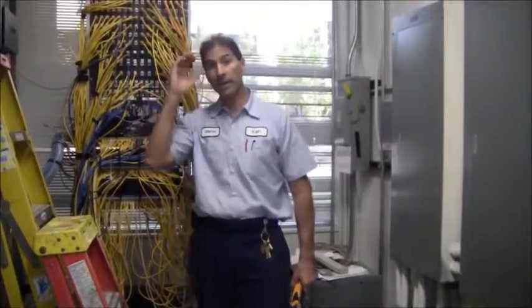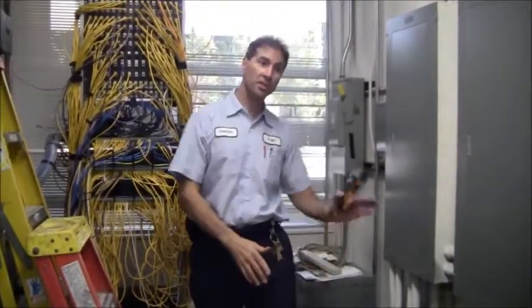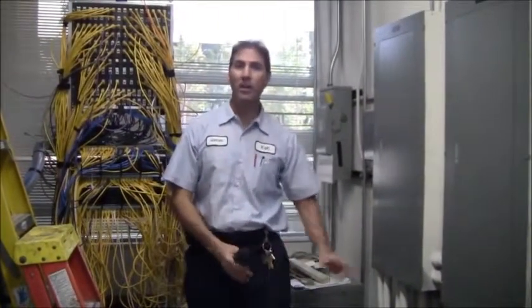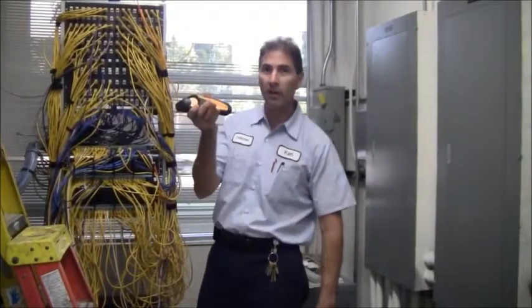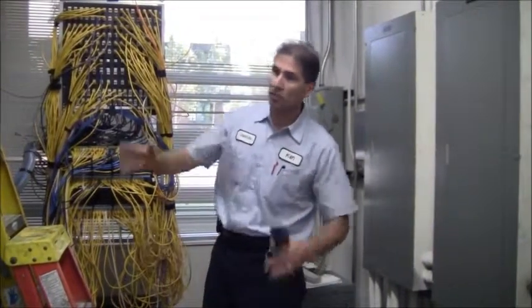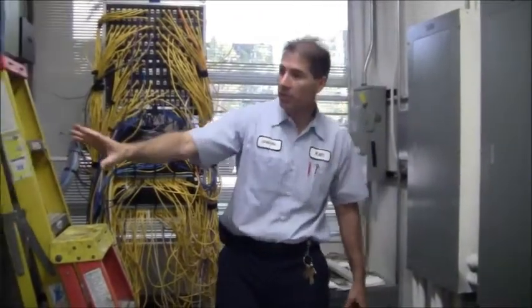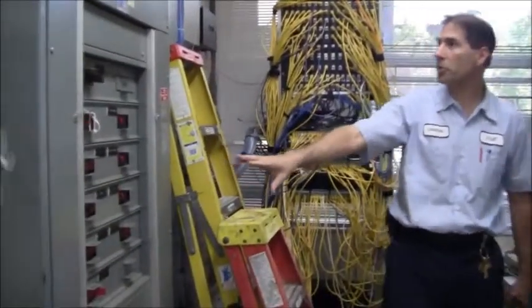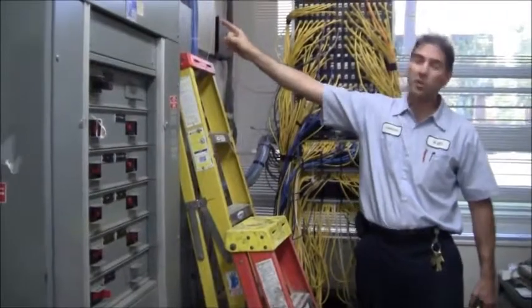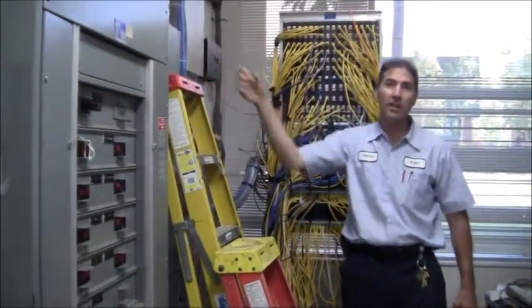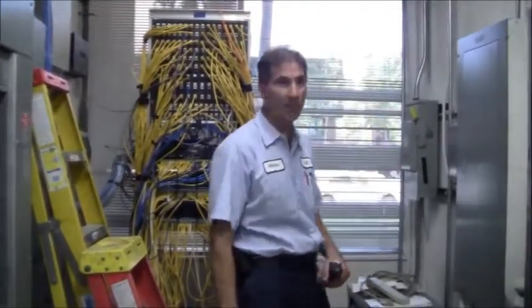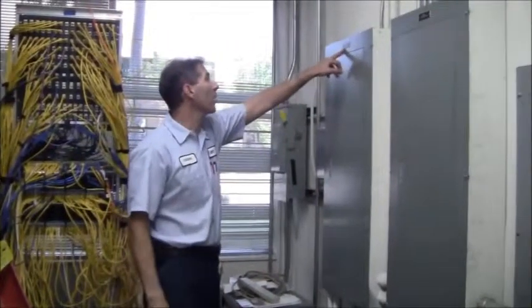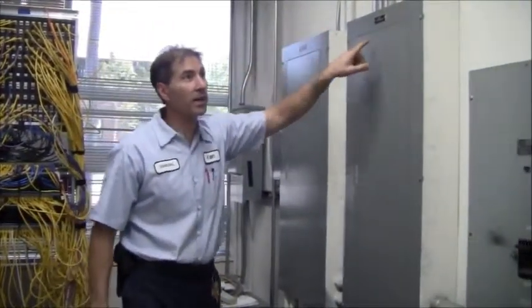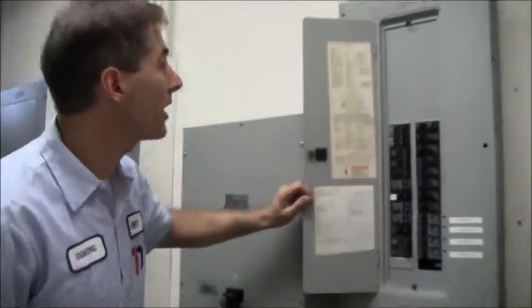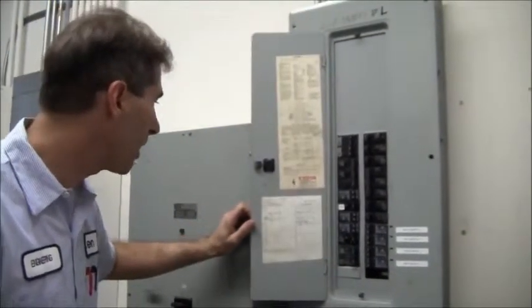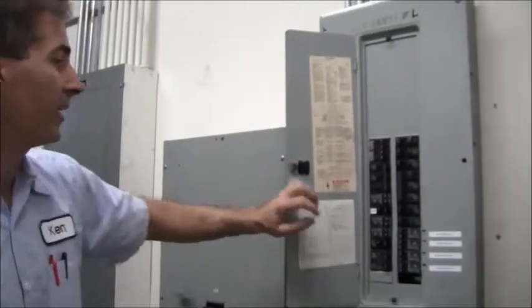Alright, I am now in the electrical room closest to where my transmitter is for the circuit breaker finder. There are service panels here. The probability is it's not going to be this distribution board - this electrical panel is 277 volt, and I'm dealing with 110 volts. This one is 120/208, this one is also 120/208, and this one here is also 120. So it could be any one of these three.